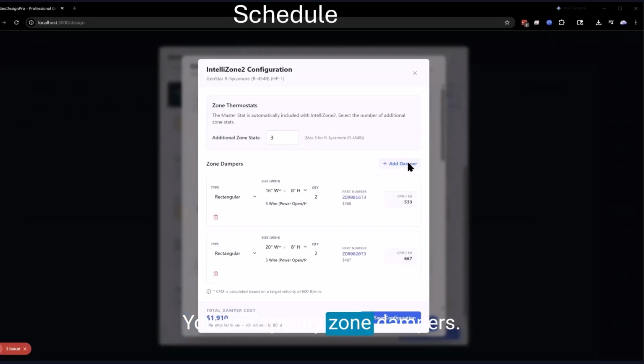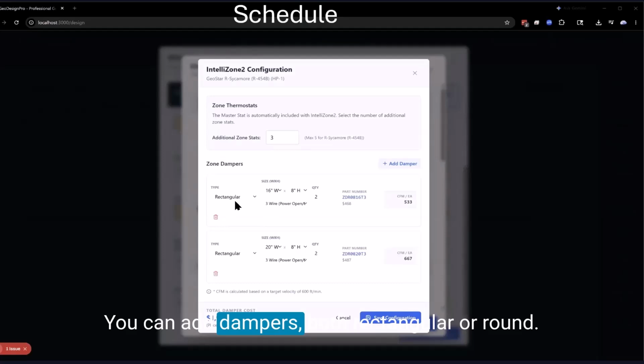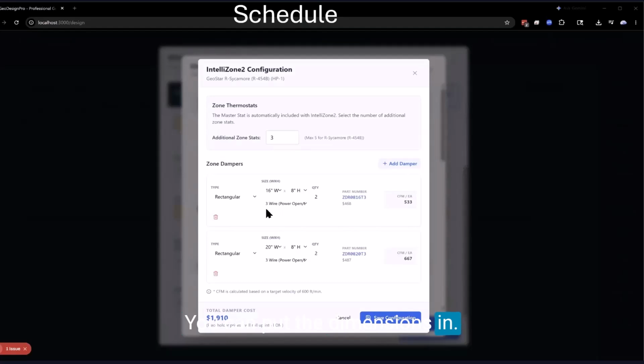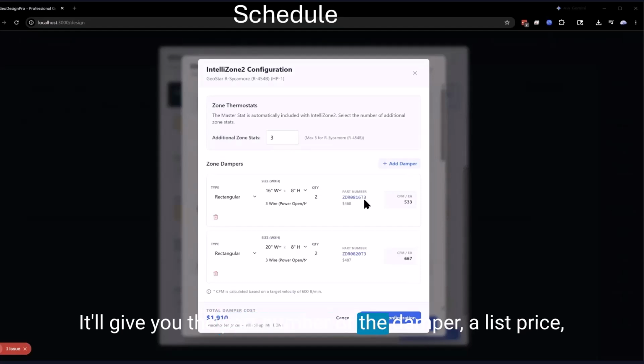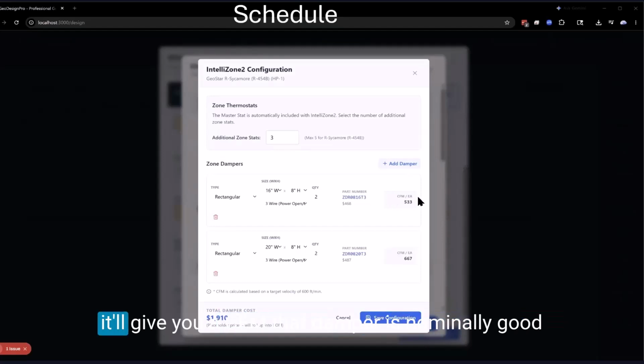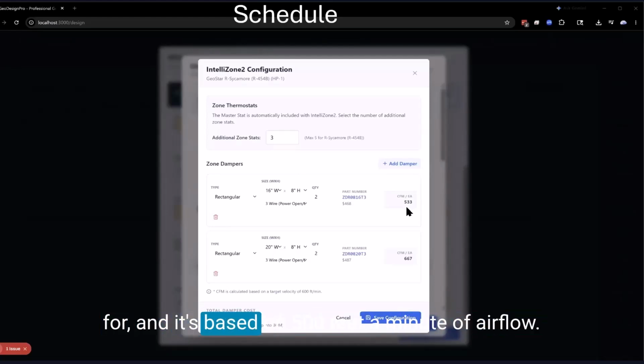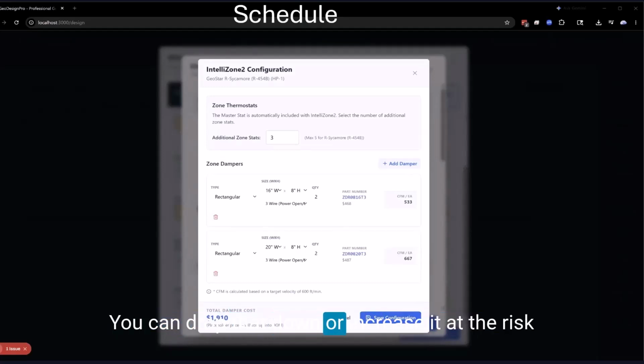You can specify zone dampers. You can add dampers, both rectangular or round. You can put the dimensions in. You can specify 3-wire or 2-wire. It'll give you the part number of the damper, a list price. It'll give you a CFM that damper is nominally good for, and it's based on 500 feet a minute of airflow. You can drop that down or increase it at the risk of potentially adding noise if you go too high. Configure the full system, get the list price of this package.